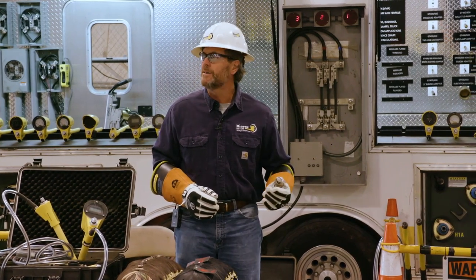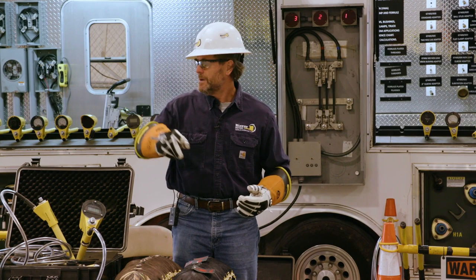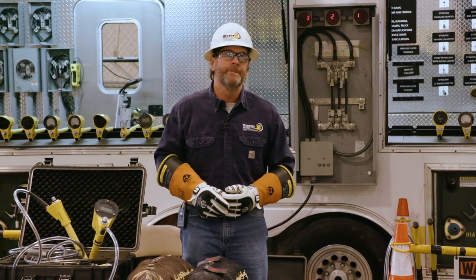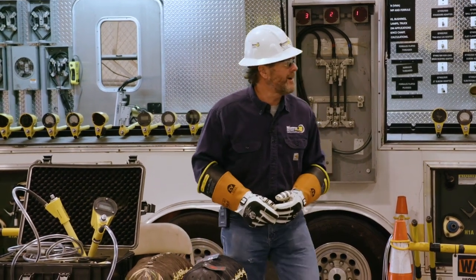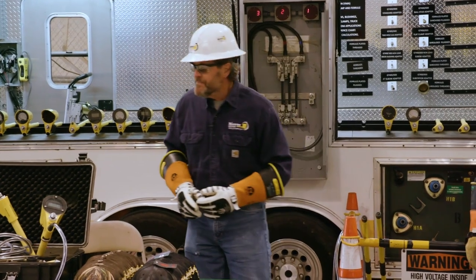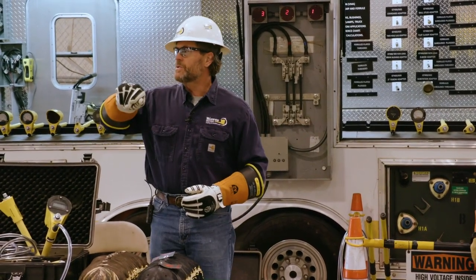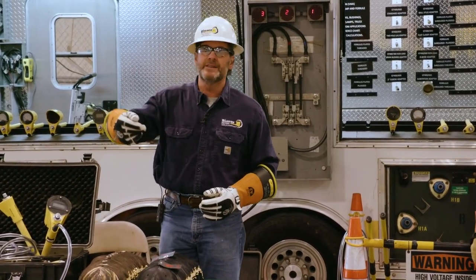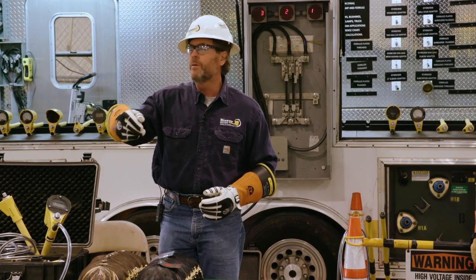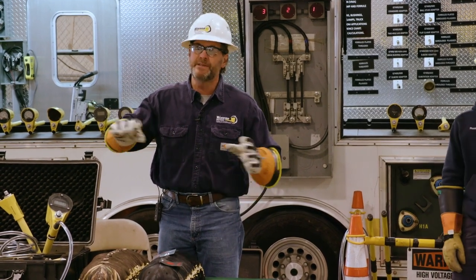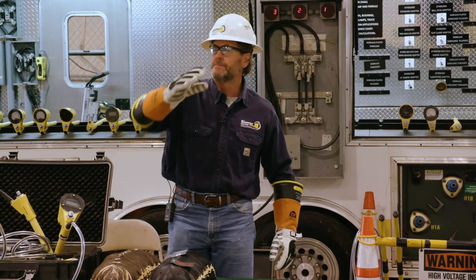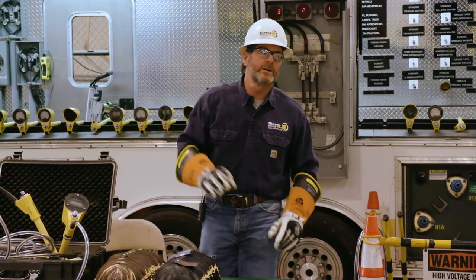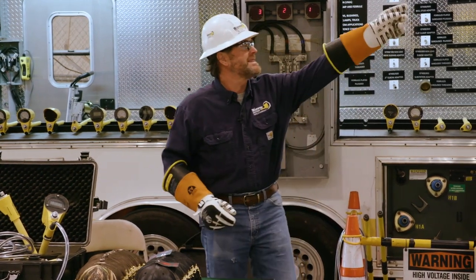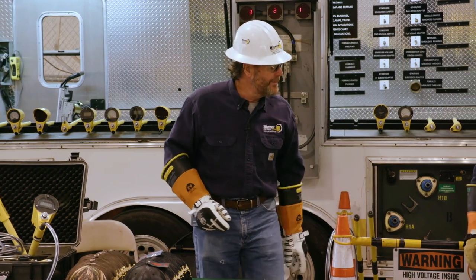Mr. Robbie and I are going to do wireless phasing with your tool, the PD800W. So remember, when you're doing wireless phasing, you always want to take your tool and put it in the degree position, not URD, not overhead, because we're not looking at potential, we're looking at phase angle. That's it. So you're going to take your reference probe that's hanging up there and your meter probe here, I'll get this ready.